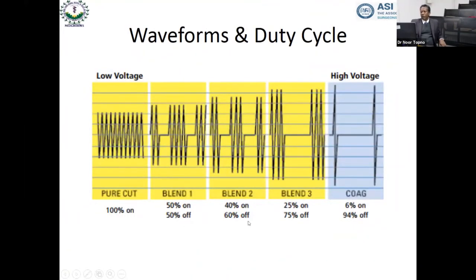I will not really go into the details of this, but I'll just give you a gist of what exactly is meant by these waveforms. Waveform is the distribution of energy, whether it is low voltage or high voltage. And this is continuous here, here it is interrupted, and here the interruption is much more. So when you talk about pure cutting current, the flow of current is continuous. There is no gap in the flow, and the voltage used is low. When you go to the other end of the spectrum, here you find that the current that is used is high voltage, and there is a huge gap between this wave and this wave.